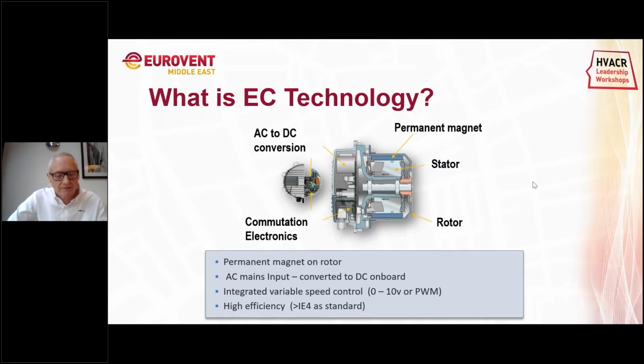Put simply, EC fans are around 30% more efficient than AC motors because the secondary magnet field comes from the permanent magnets rather than the copper windings. This really is a major factor with an EC fan - the permanent magnet. An AC motor consumes additional energy solely to create a magnetic field by inducing the current in the rotor.